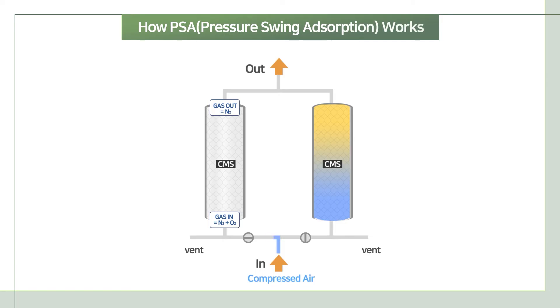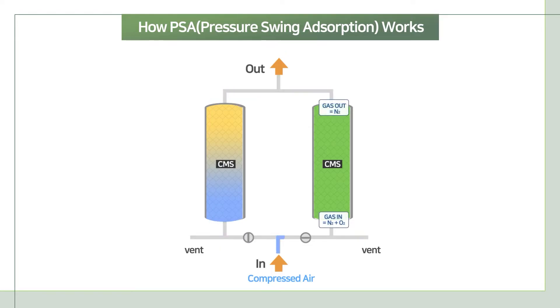When compressed air gets into one of the CMS columns to be separated, it adsorbs oxygen at the pore of CMS, while the other column desorbs them to be regenerated for the next round. The generator switches these two columns between adsorption and desorption for semi-permanent use.